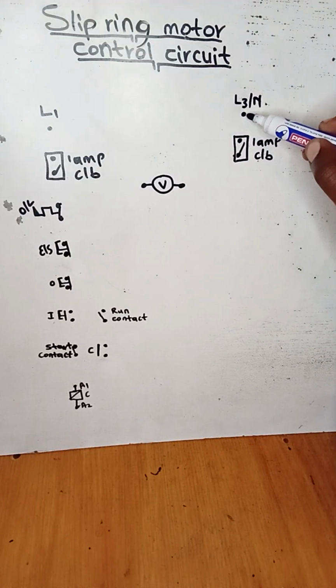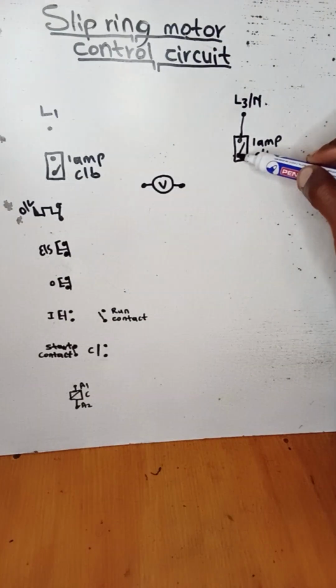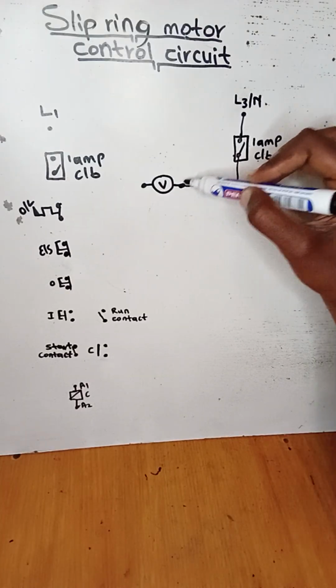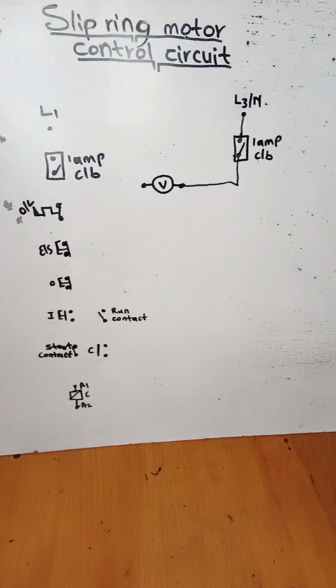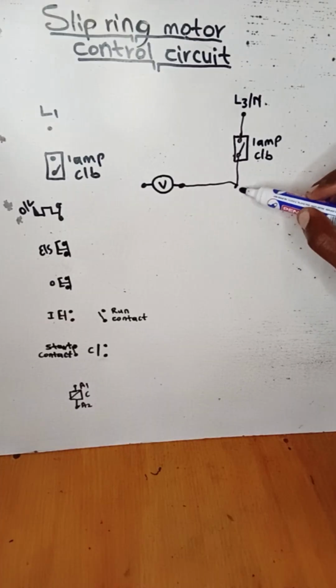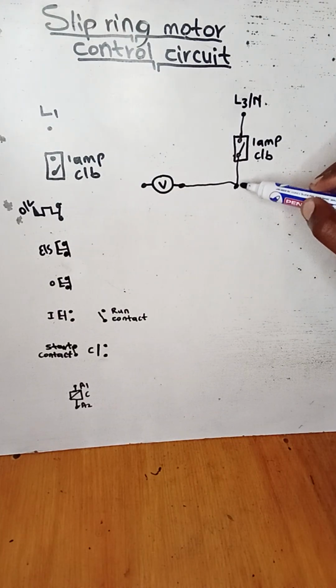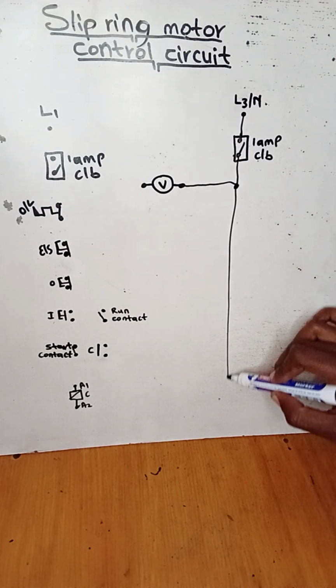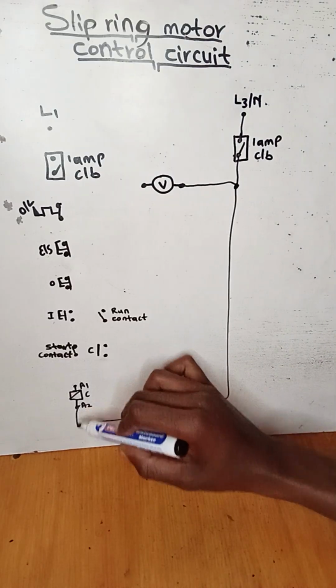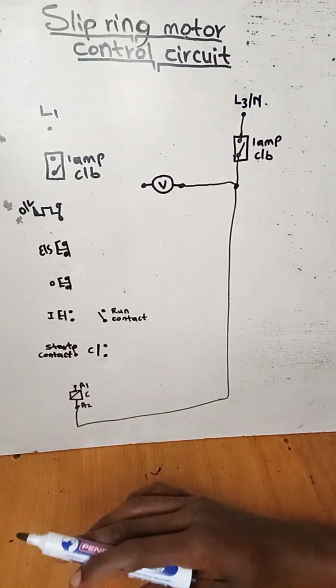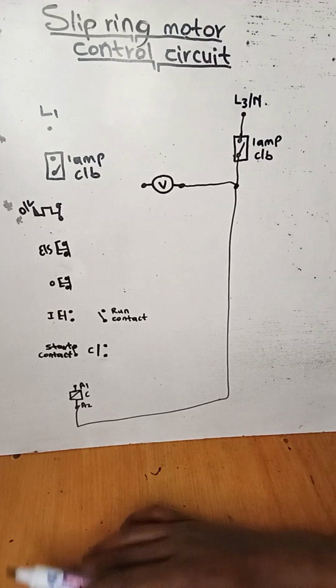From the supply voltage of live 3, it will go to the in point of the 1 amp circuit breaker and the out point of the 1 amp circuit breaker to the overload, and then it will also be looped to the A2 of the coil, and that is it about the wire of live 3.